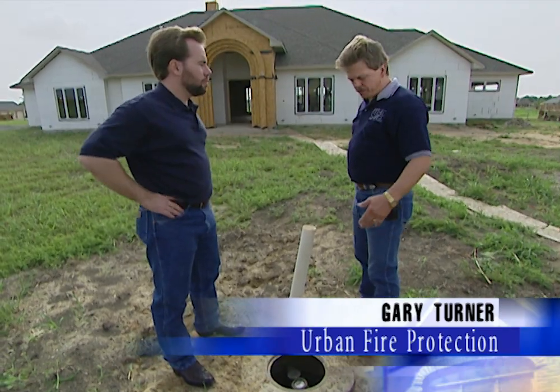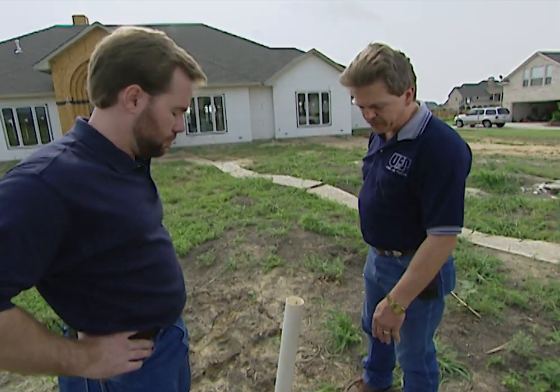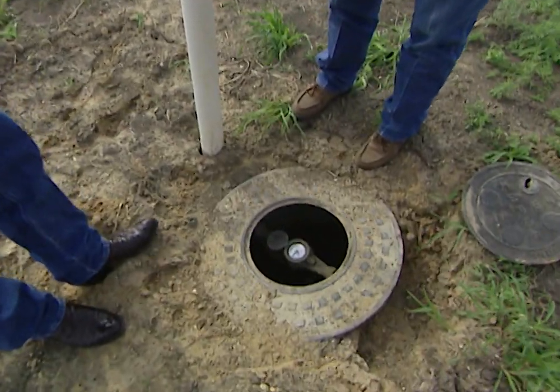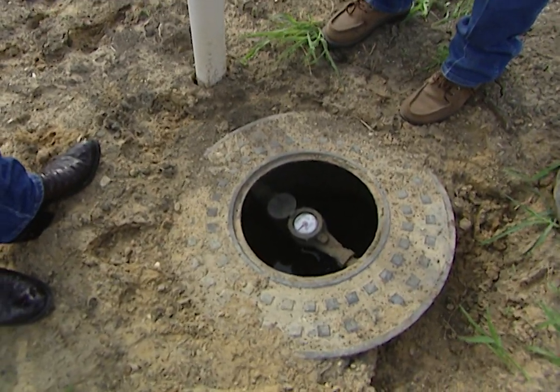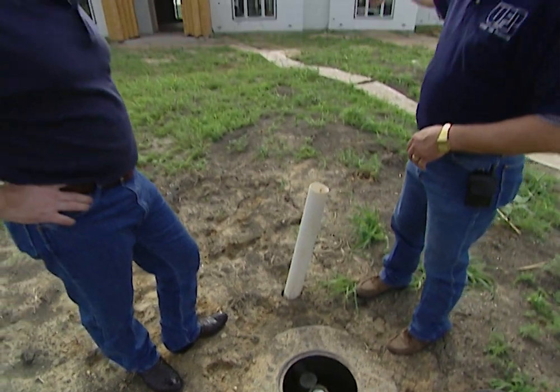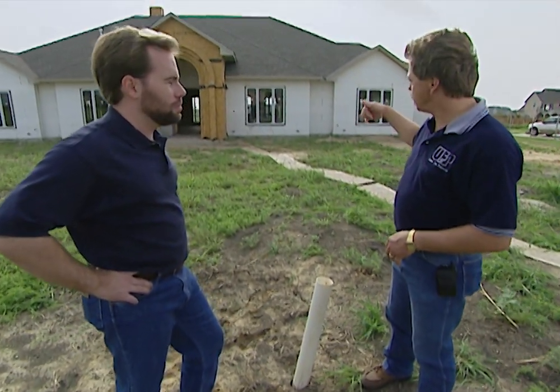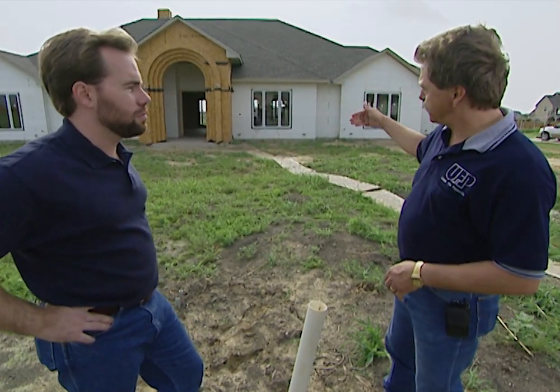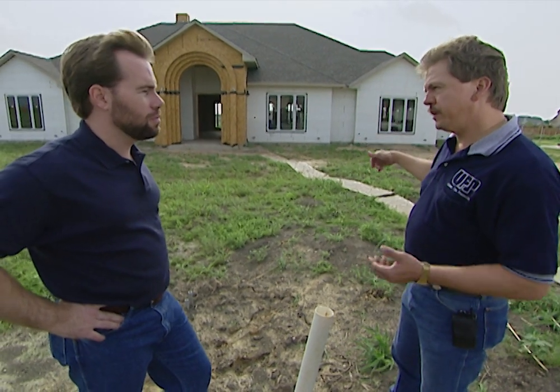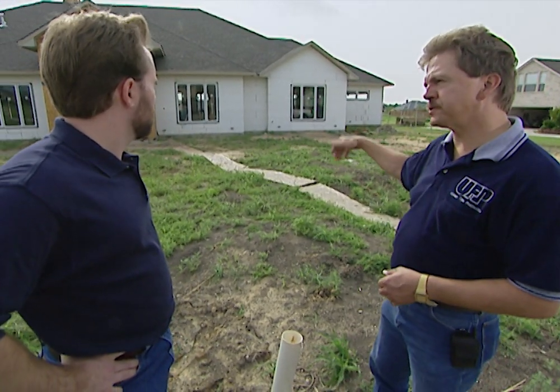Yeah, Michael, what normally happens is the domestic line taps the city main, runs to the meter, and then there's a line from the water meter to the cutoff valves just outside the grade beam of the home, which supplies the domestic water. About a foot or so this side of the grade beam, between the water meter and the domestic cutoff valve, is where the fire sprinkler system supply taps in and makes its connection, and then there's a dedicated line that runs from the domestic water supply to the fire sprinkler riser location.